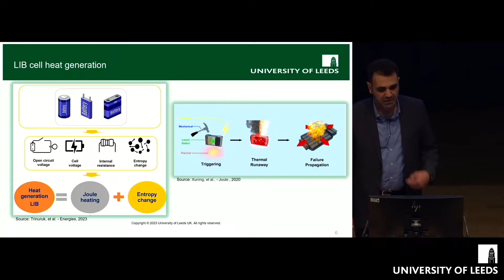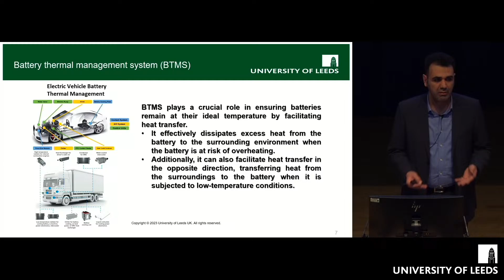A battery thermal management system (BTMS) is not just the cooling system itself. In general, it includes components such as the cooling system, heat sink, heat exchanger, fan, pumps, temperature sensor, expansion tank, and control valves, all of which together manage and keep the battery's temperature within an acceptable range.